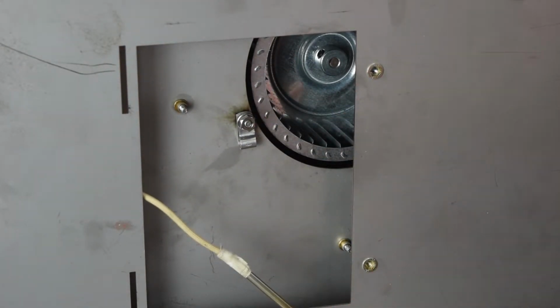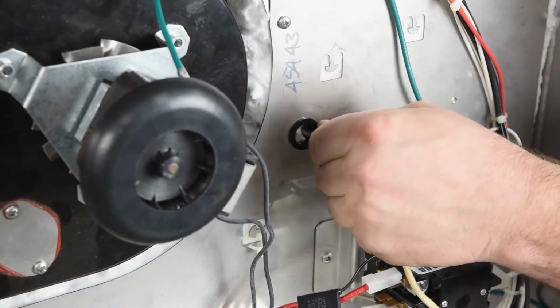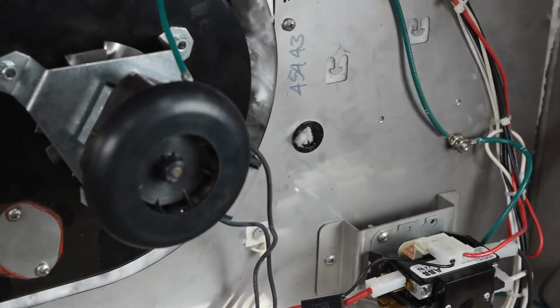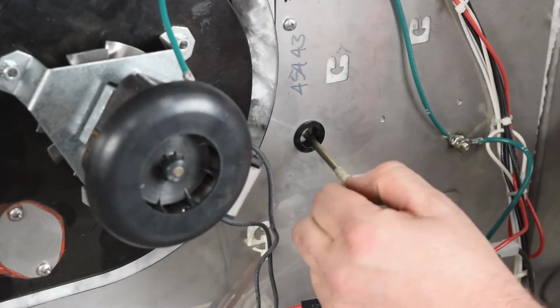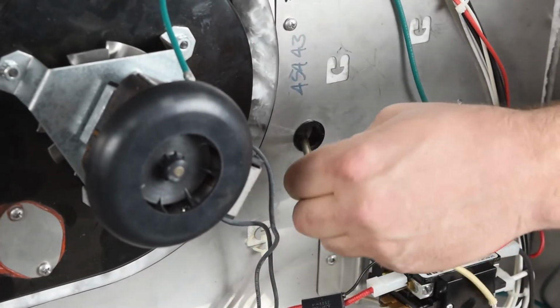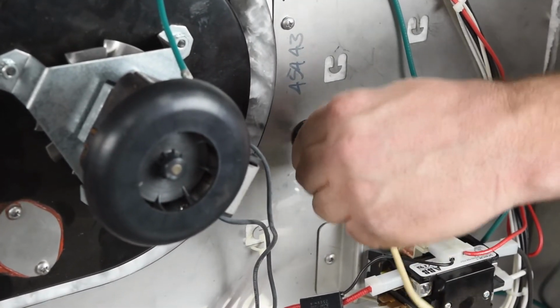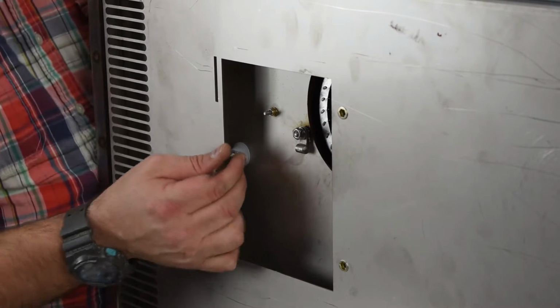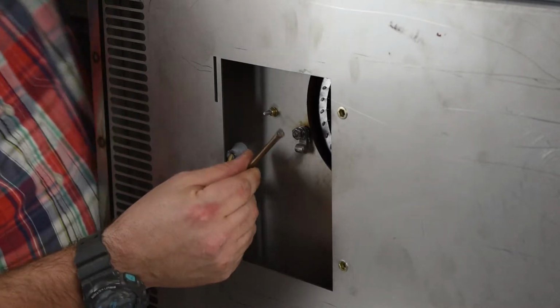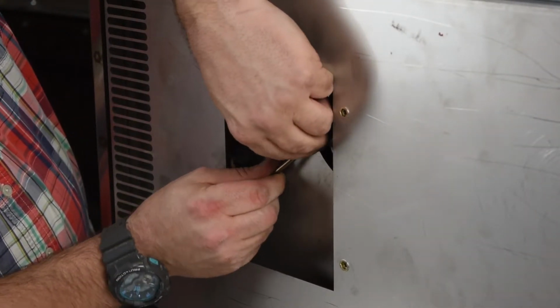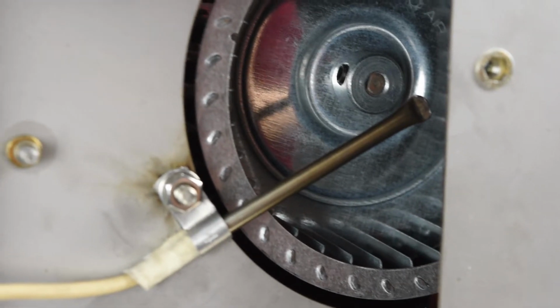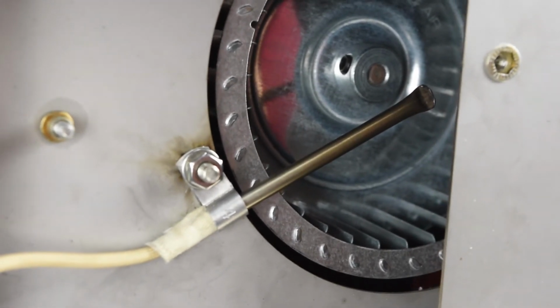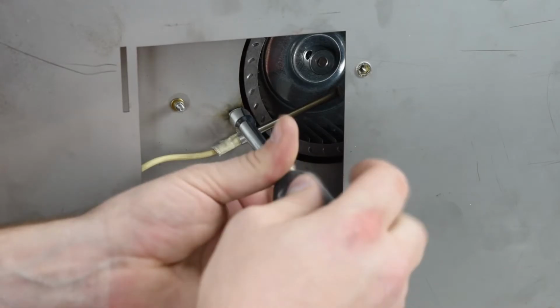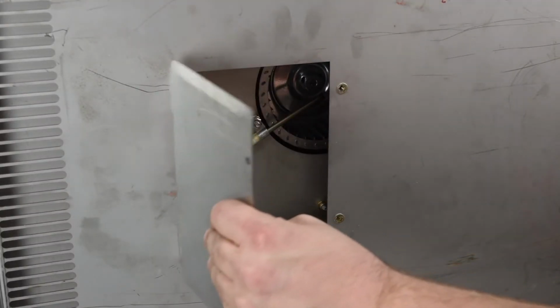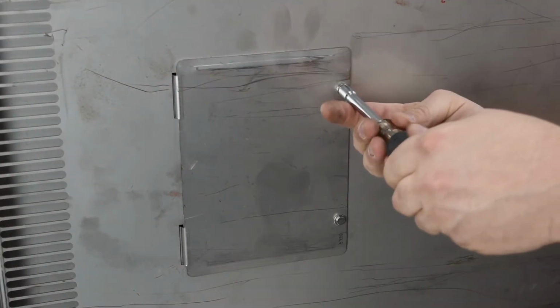Behind the steel paneling there is a rubber grommet leading to the top of the unit where you unplug the probe. Guide the probe through that hole and set it aside. Grab the new probe and feed it through the top of the unit and through the P-clip, where the end of the probe is in line with the central shaft of the blower motor. Secure the probe with a 3/8" nut and reinstall the cover and the 2 5/16" nuts.